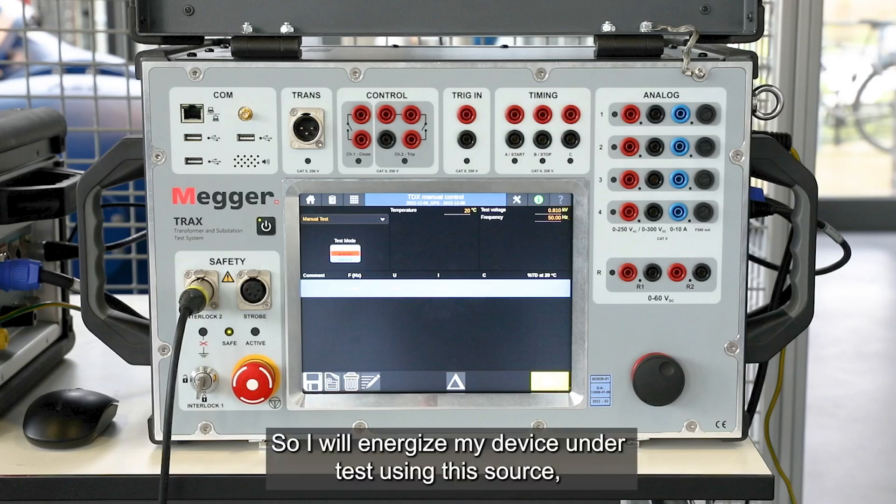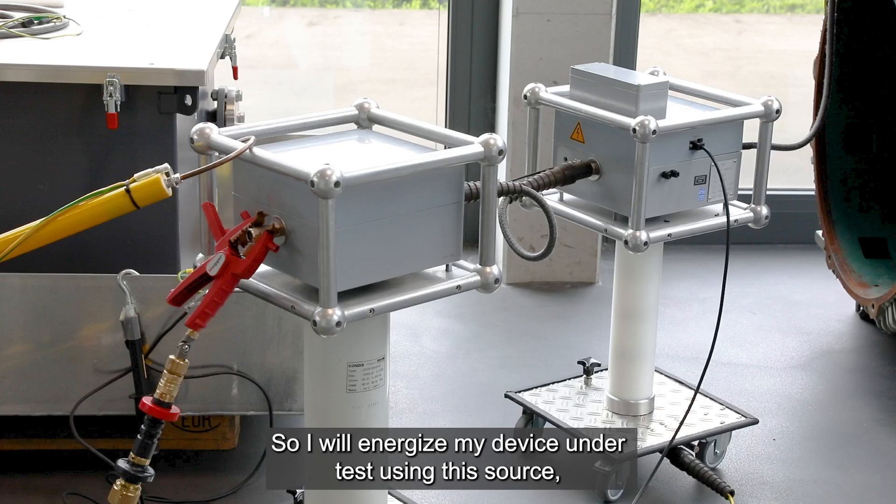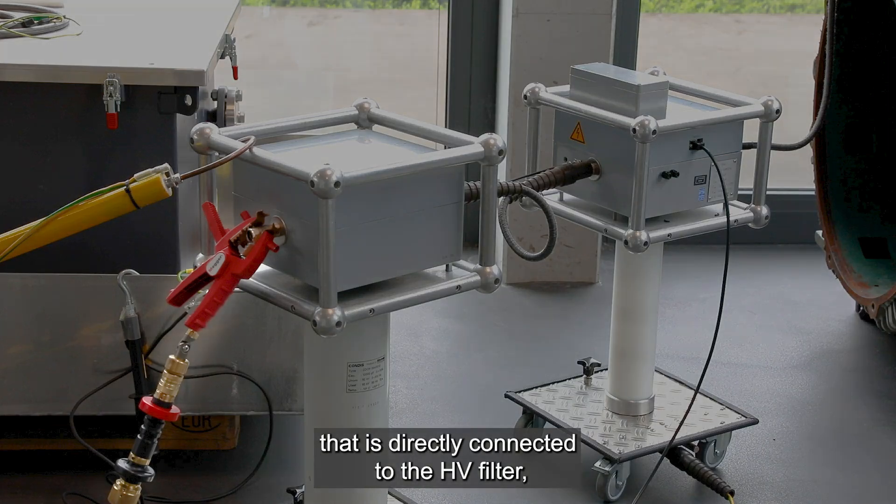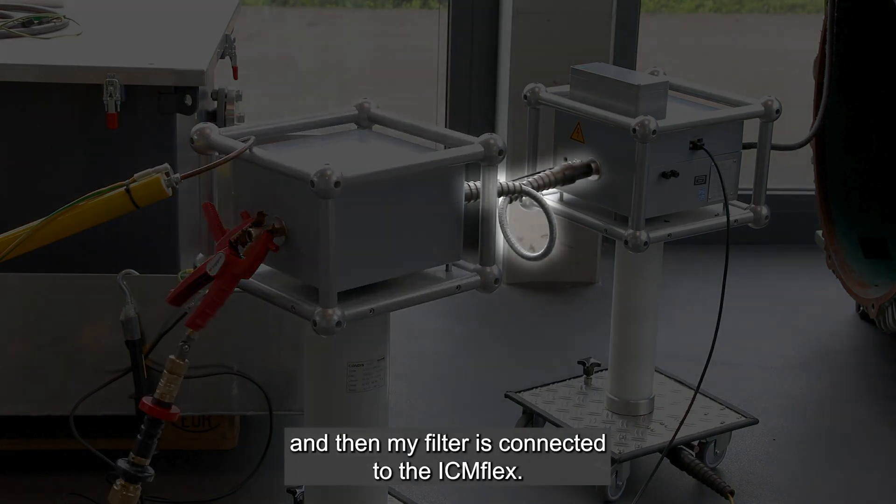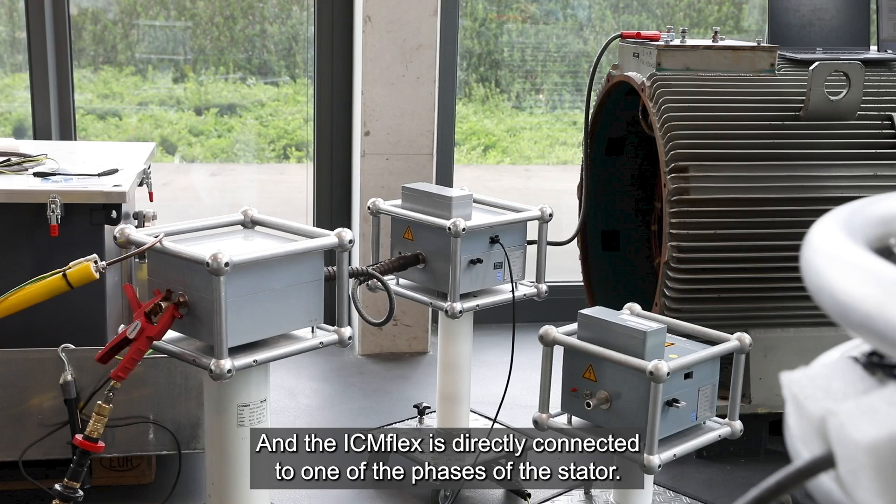So I will energize my device under test using this source that is directly connected to the HV filter. And then my filter is connected to the ICM Flex. And the ICM Flex is directly connected to one of the phases of the stator.